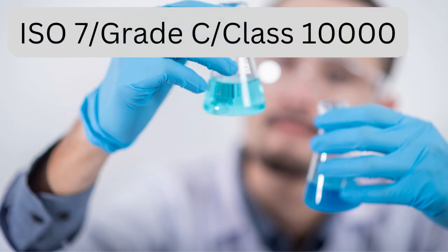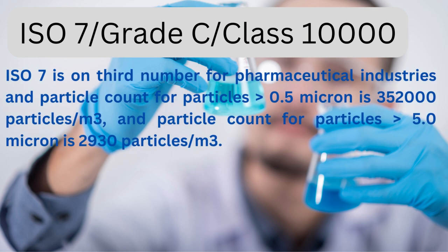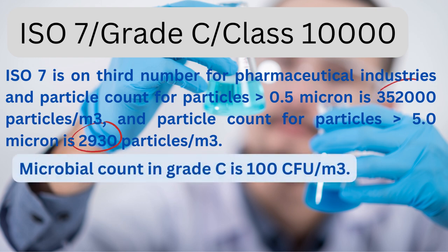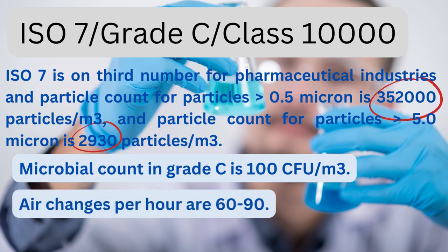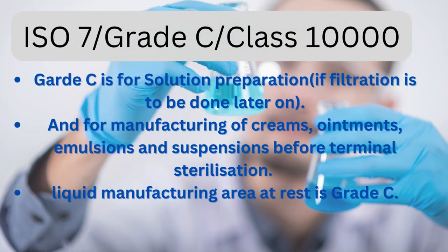Third is ISO 7, corresponding to Grade C or Class 10,000. Particle count for particles greater than 0.5 micron is 352,000 particles per cubic meter, and particle count for particles greater than 5.0 micron is 2,930 particles per cubic meter. Microbial count in Grade C is 100 CFU per cubic meter. Air changes per hour are 60 to 90. Grade C is for solution preparation if filtration is to be done later on, and for manufacturing of creams, ointments, emulsions, and suspensions before terminal sterilization. Liquid manufacturing area at rest is Grade C.